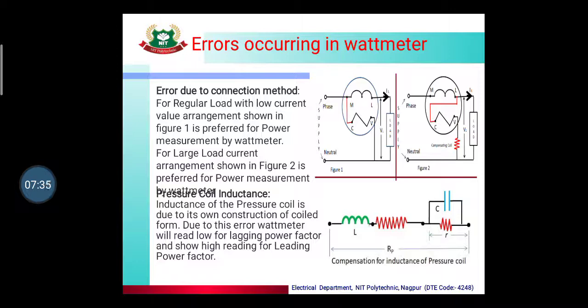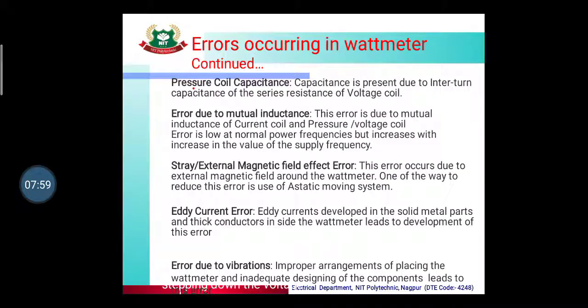The third error is pressure coil capacitance, which is present due to inter-turn capacitance of the series resistance of the voltage coil. The fourth error is error due to mutual inductance between the current coil and the pressure coil. This error is low at normal power frequency, but as the supply frequency increases, this error also increases.